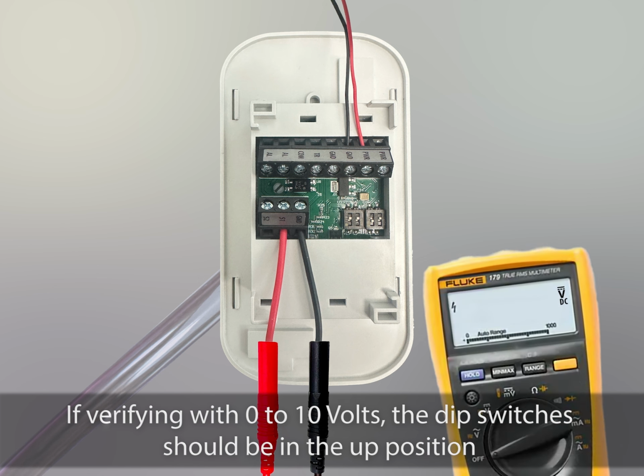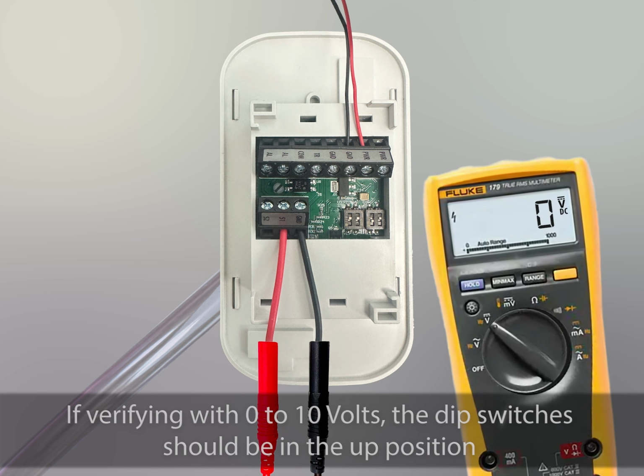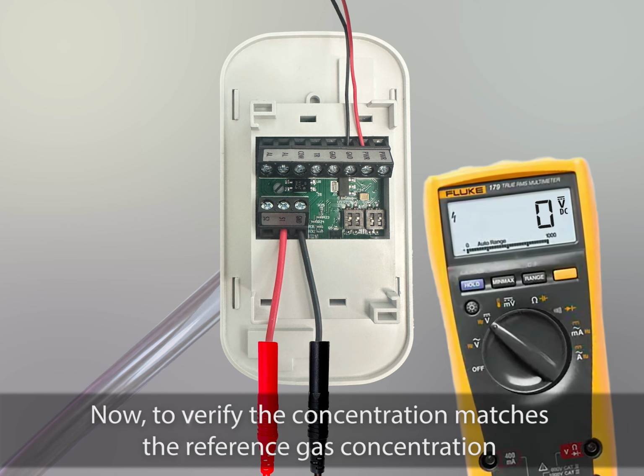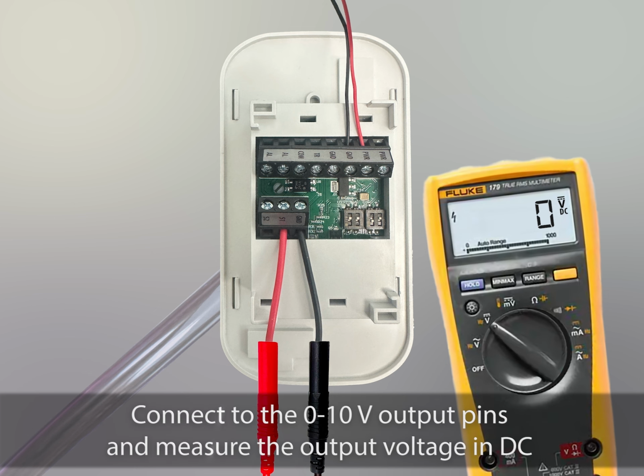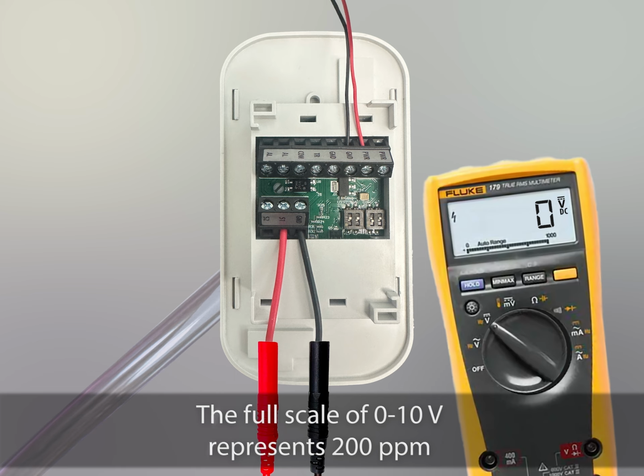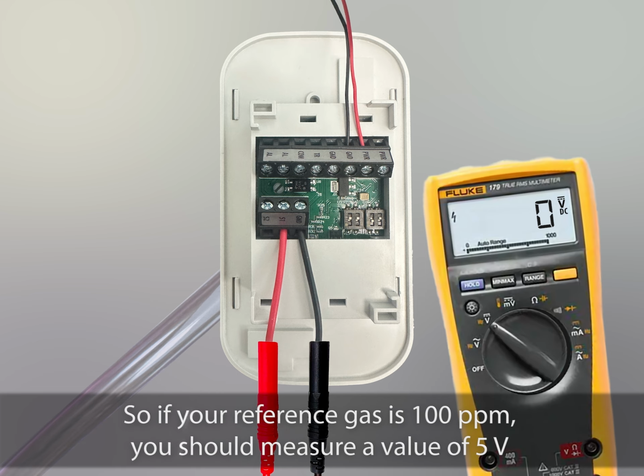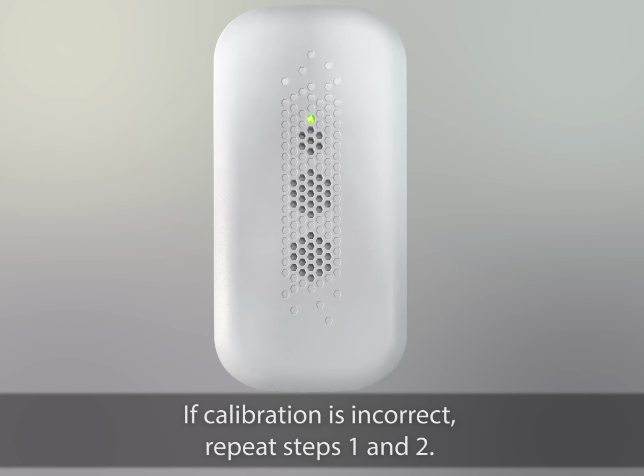If verifying with 0 to 10 volts, the DIP switches should be in the up position. Now, to verify the concentration matches the reference gas concentration, connect to the 0 to 10 volt output pins and measure the output voltage in DC. The full scale of 0 to 10 volt represents 200 parts per million. So if your reference gas is 100 parts per million, you should measure a value of 5 volts. If calibration is incorrect, repeat the first 2 steps.